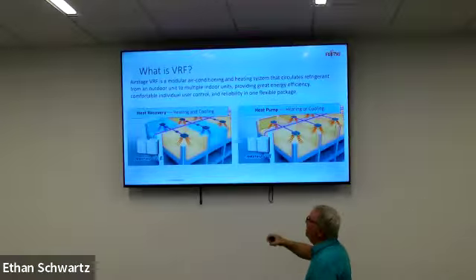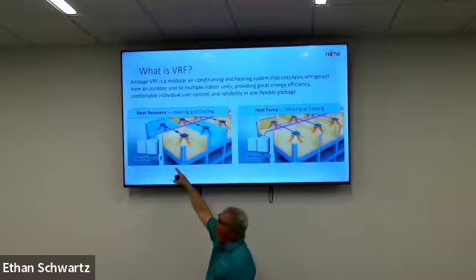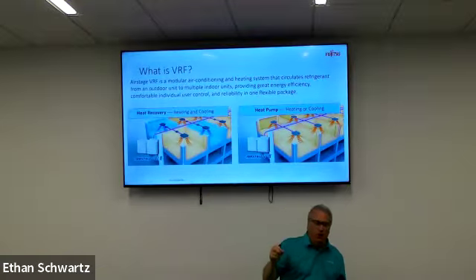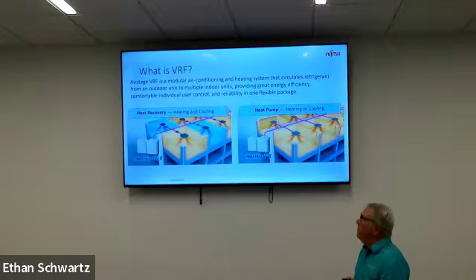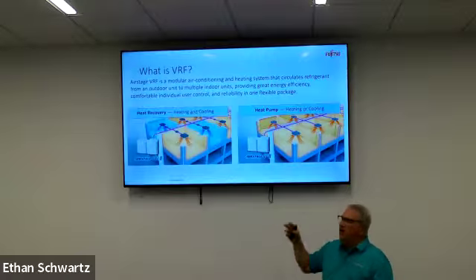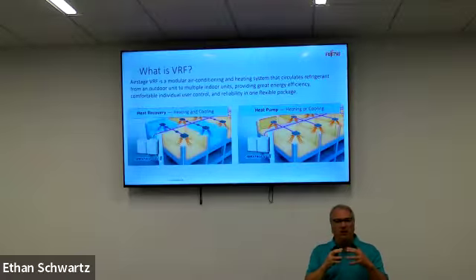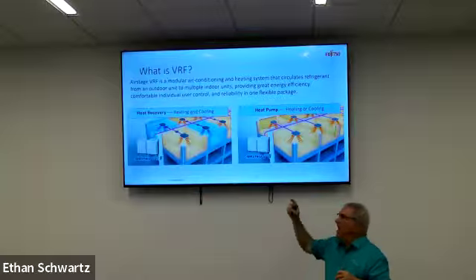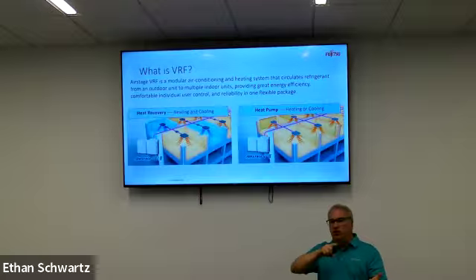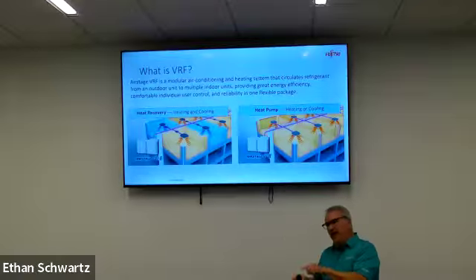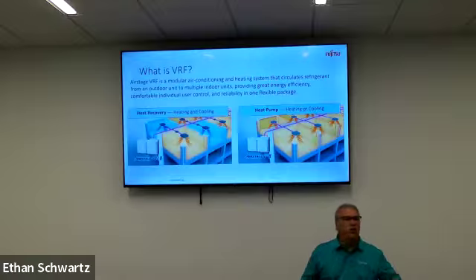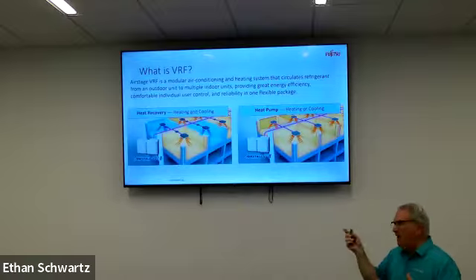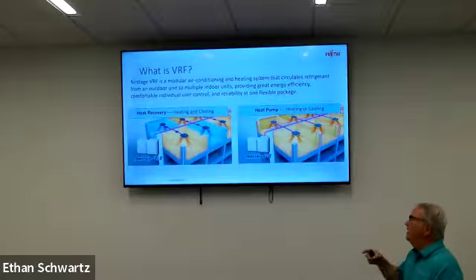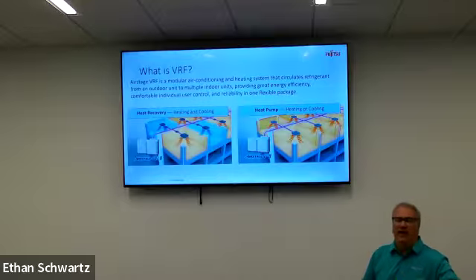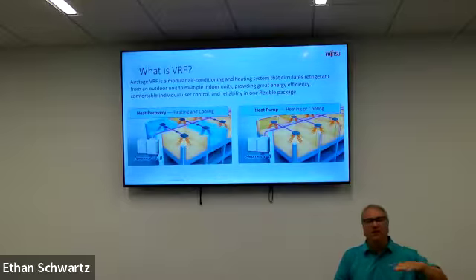The beauty of that is that there are some times if you have an equal load on heat recovery, where you have roughly the same amount of BTUs in heating as in cooling, the compressor becomes merely a device that's going to create a pressure differential in the piping and then allow the equipment to just move that refrigerant, liquid back to gas, gas going through the compressor back to liquid, and then go back to a high pressure gas, and then go back to a liquid, and that will then limit the amount of energy.